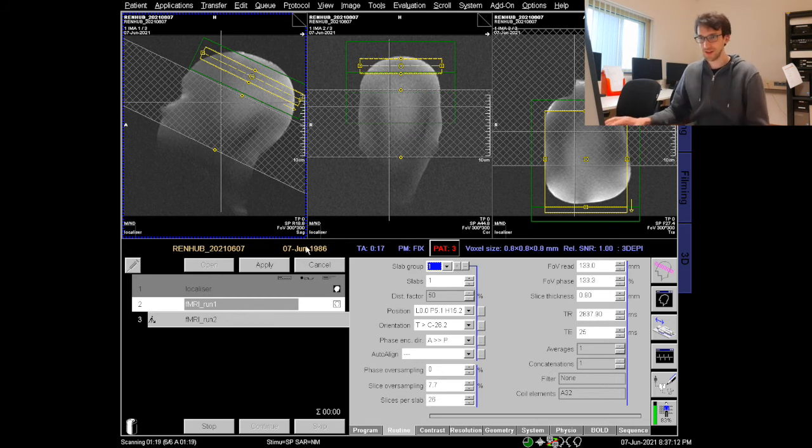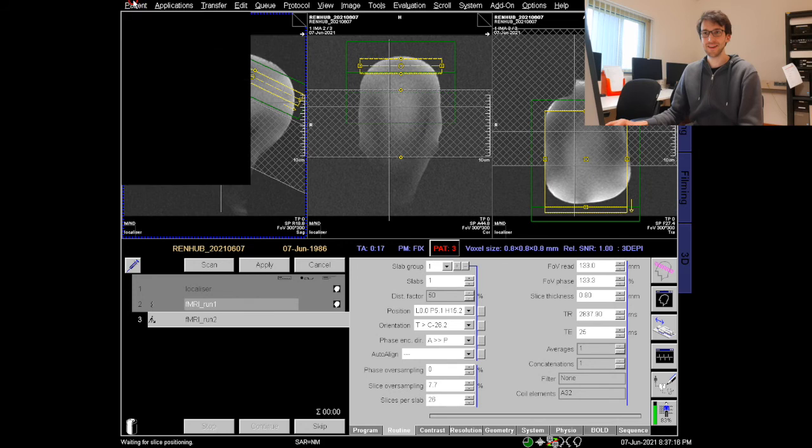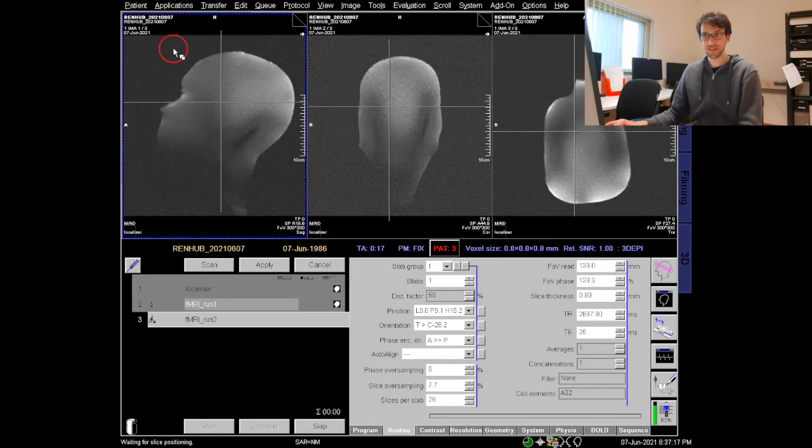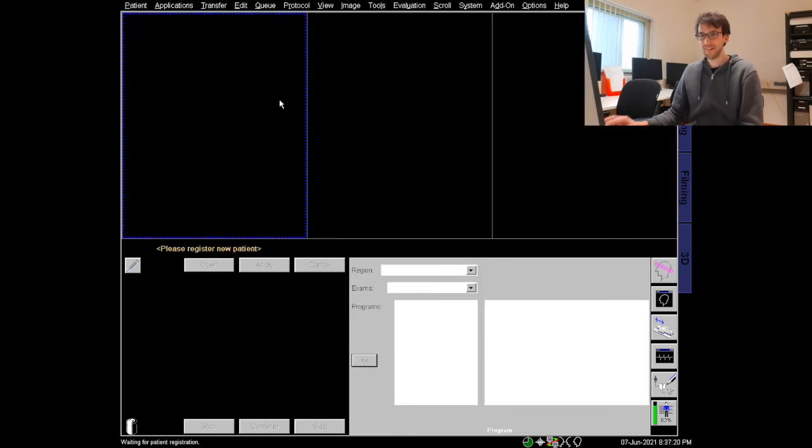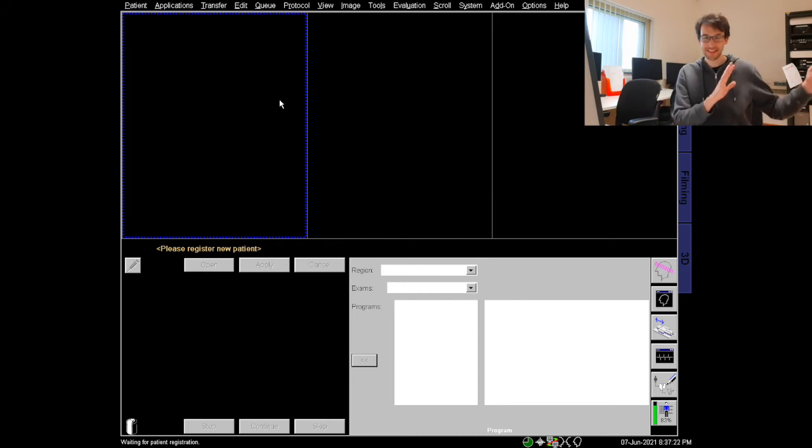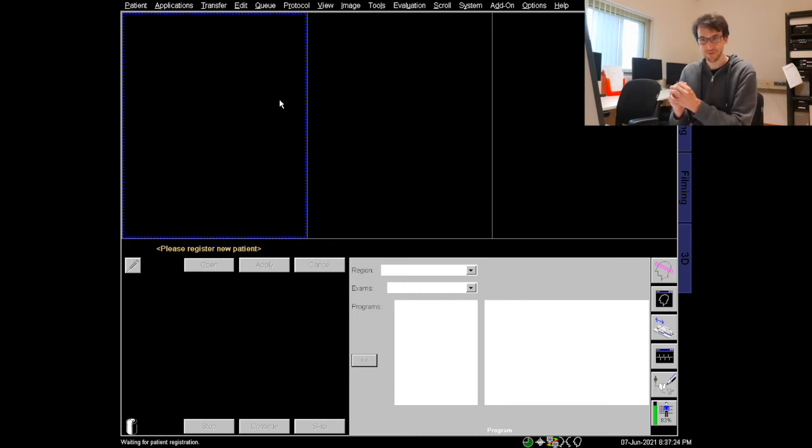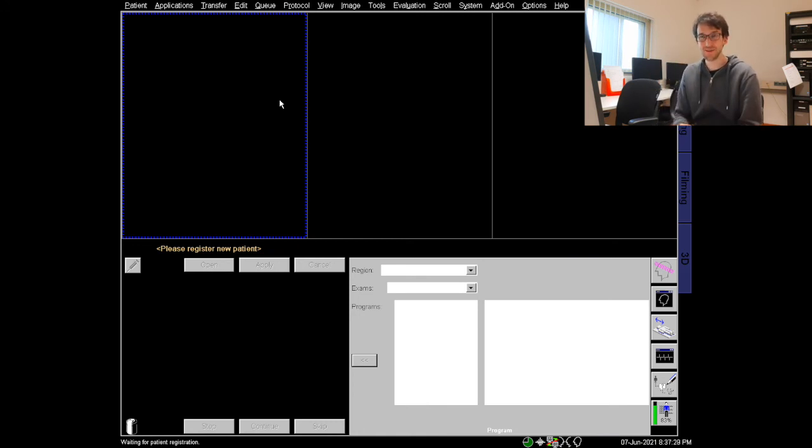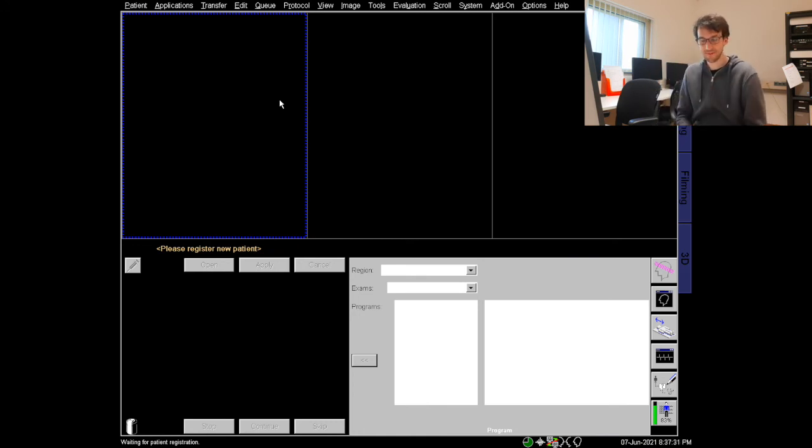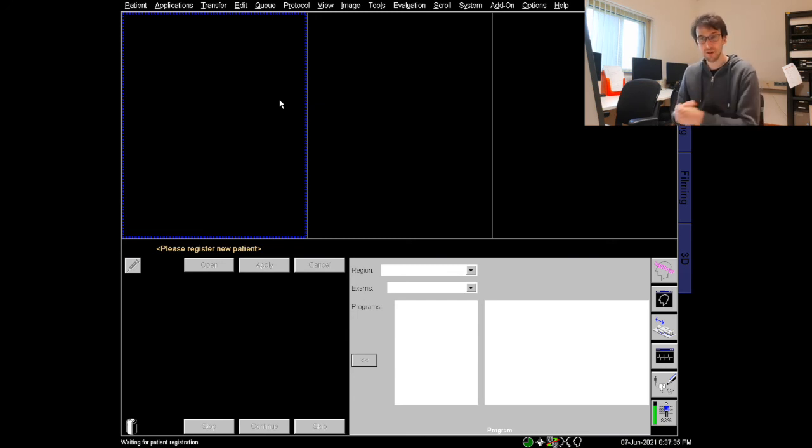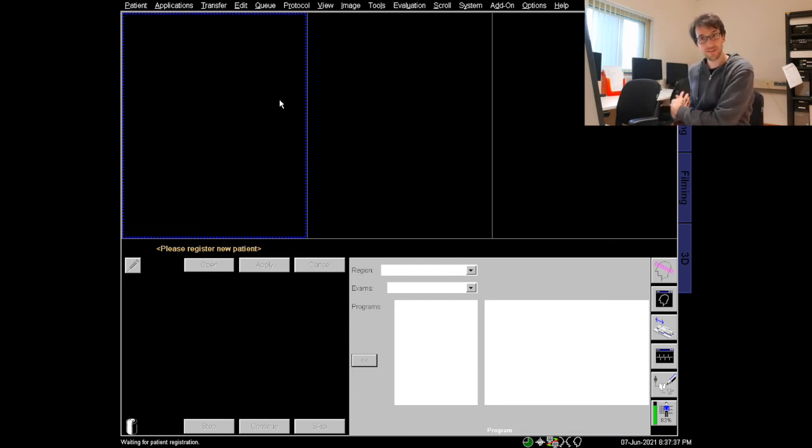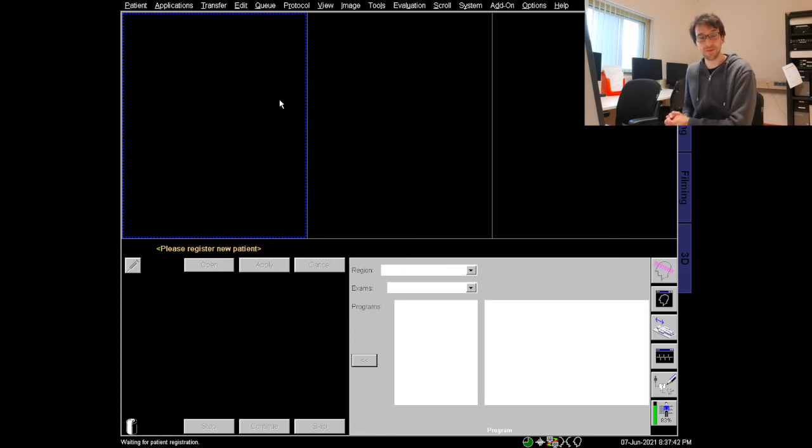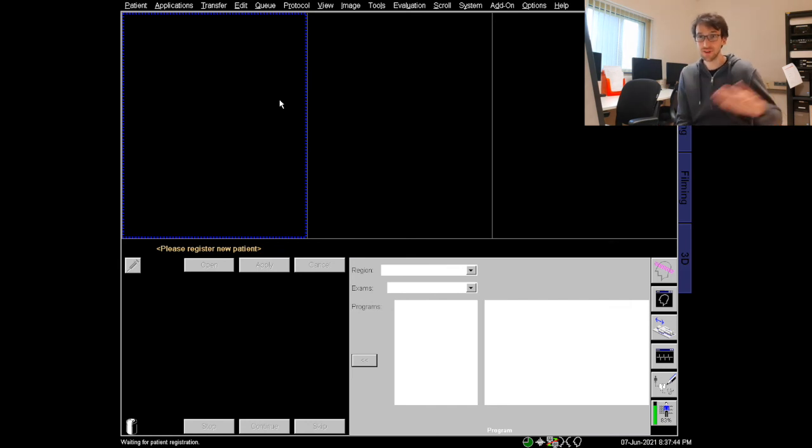Let's assume we are done with that and we are happy with our experiments so we can stop our scan and we can close our patient. So now everything looks like we can leave the scanner right? This is not true. We still didn't close the third order shim interface and also we didn't turn it off again. So we need to do this and we should really not forget this because other people scanning after us will have suboptimal shim currents if we don't switch it off. They will also have suboptimal second order shim currents if we don't switch off the third order shim.